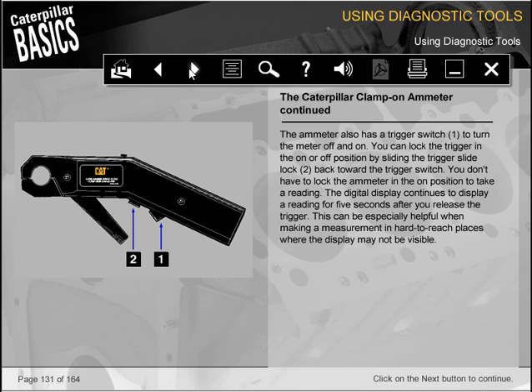The ammeter also has a trigger switch, 1, to turn the meter off and on. You can lock the trigger in the on or off position by sliding the trigger slide lock, 2, back toward the trigger switch. You don't have to lock the ammeter in the on position to take a reading. The digital display continues to display a reading for 5 seconds after you release the trigger. This can be especially helpful when making a measurement in hard-to-reach places where the display may not be visible.